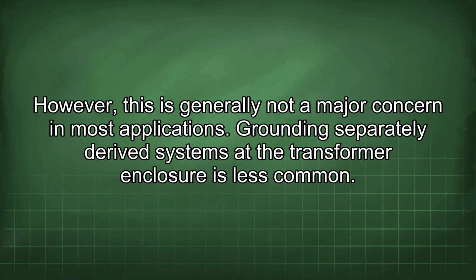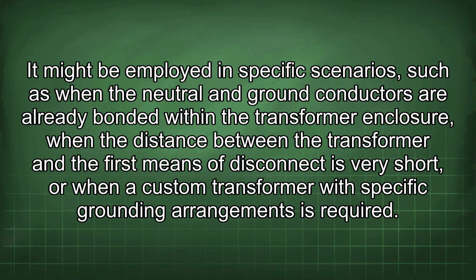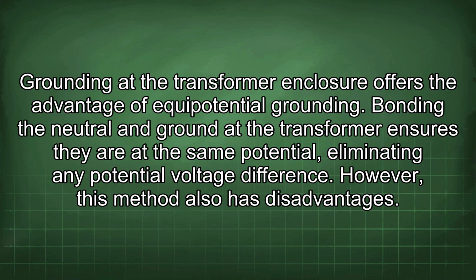However, this is generally not a major concern in most applications. Grounding separately derived systems at the transformer enclosure is less common. It might be employed in specific scenarios, such as when the neutral and ground conductors are already bonded within the transformer enclosure, when the distance between the transformer and the first means of disconnect is very short, or when a custom transformer with specific grounding arrangements is required. Grounding at the transformer enclosure offers the advantage of equipotential grounding. Bonding the neutral and ground at the transformer ensures they are at the same potential, eliminating any potential voltage difference.